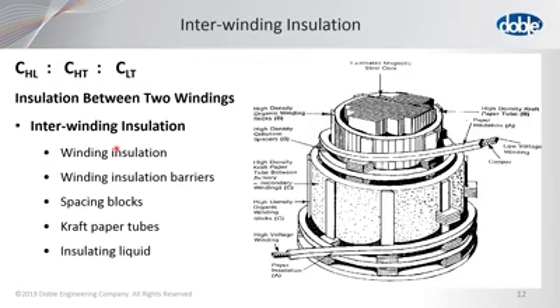But that's something that you need to look in the instruction manual for the insulation resistance test very carefully to see their recommendations. Remember, I'm a Doble employee. I make recommendations on Doble tests, so be careful with the winding resistance. Now that I've said that, of course, the M7100 blurs that line a little bit, because now we are doing insulation resistance tests with the M7100. So we're going to be learning more about how we can analyze those results better.